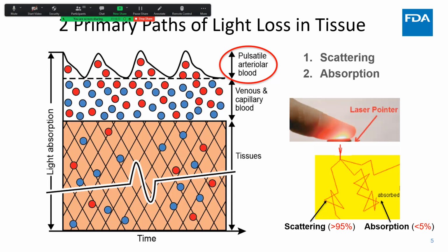So the key point to the use of these devices is that they are attempting to see a change in attenuation of light, a degradation that is in some modulated time series. And that modulation is then assumed to be the pulse rate. You can imagine that as this vessel is expanding and contracting, it absorbs a different amount of light. That's what's shown at the very top with what is referred to as a PPG, or photoplethysmograph, of that change in light attenuation. That is what is displayed as pulse rate.